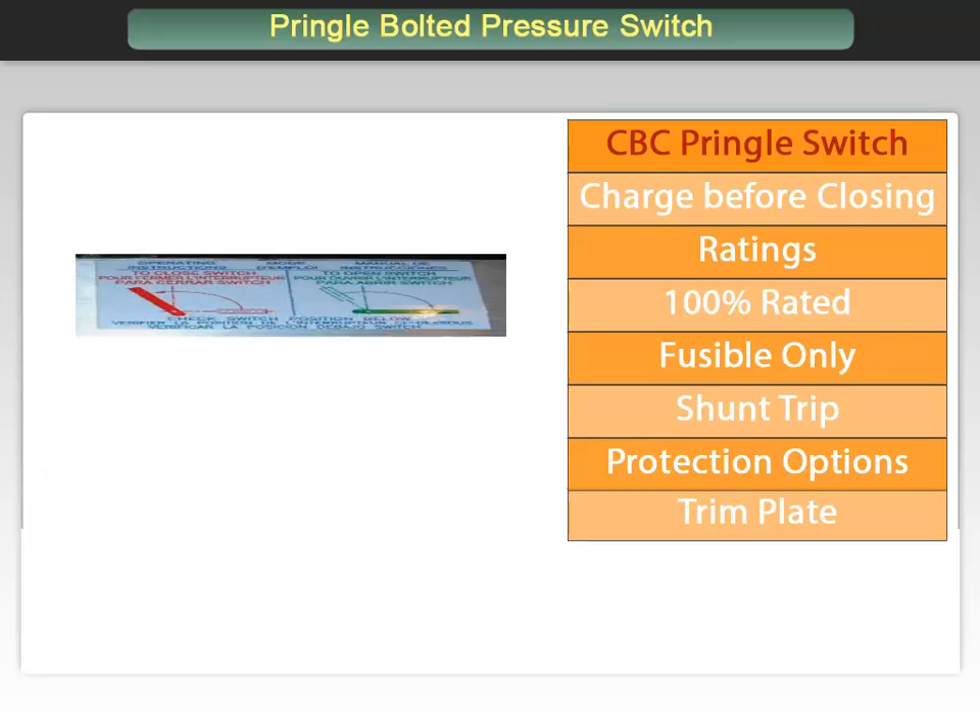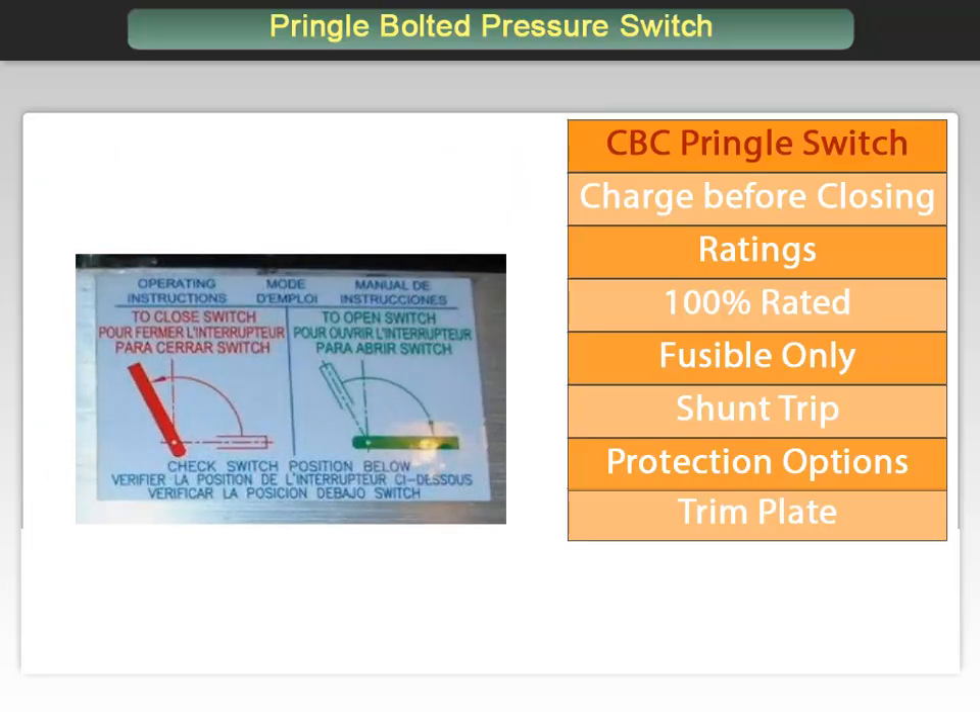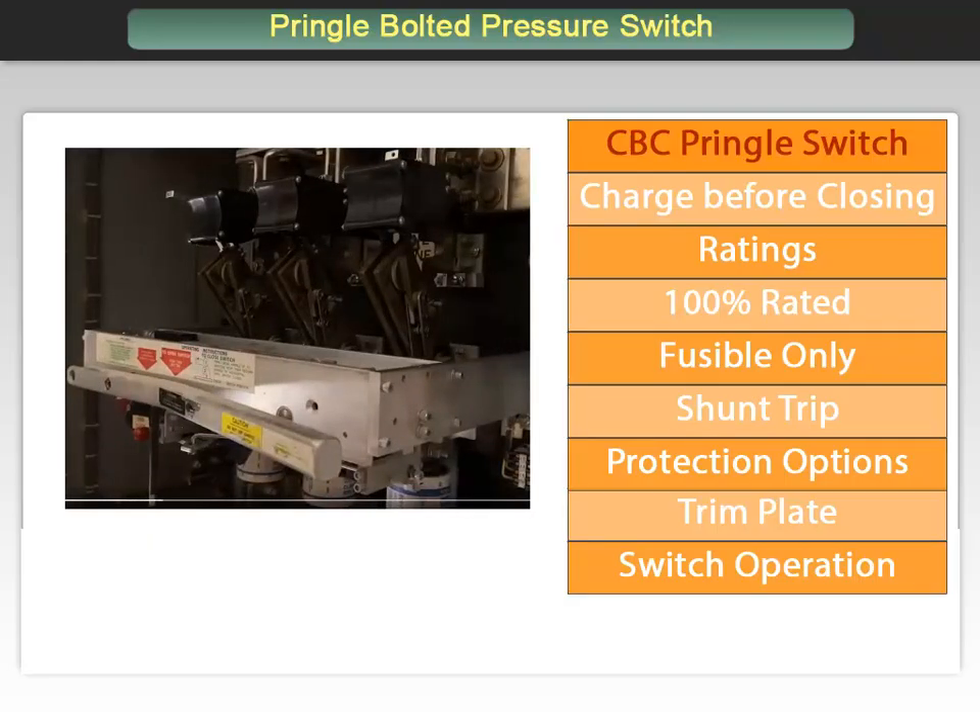Now back to the operating mechanism. As mentioned previously, the operator must charge the switch. In order to do so, the operating handle is rotated counter-clockwise, which compresses the closing spring. This charging process ensures that the switch is in a safe, charged state before it can be closed, preventing accidental or premature closing. Once the switch is closed, it can be tripped open manually by a mechanical push button or electrically by sending a signal to a solenoid. The switch features a quick-acting stored energy mechanism where the spring is released near the end of the stroke to provide quick, positive switching action regardless of the handle's operating speed. The instructions are clearly displayed on the trim plate.